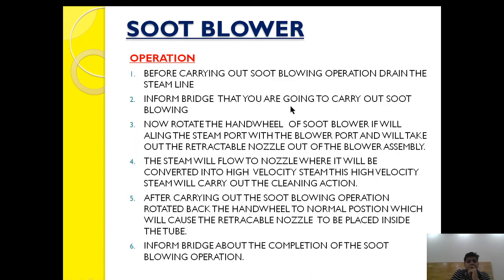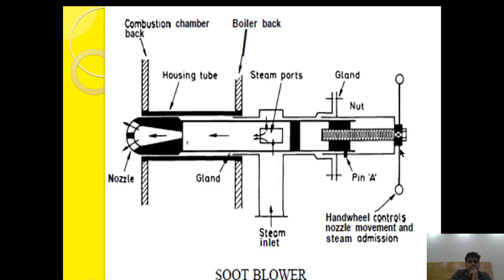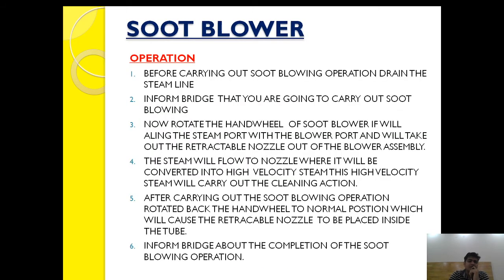Before carrying out the soot blowing operation — before you rotate the hand wheel to align the steam port with the steam inlet port — we should keep some things in mind. First: drain the steam line. This is very important because soot blowing is carried out only twice or thrice a day. As it is not a regular operation, the steam in the line may condense and change into water, which if steam is suddenly opened will cause hammering. To prevent that, we drain the steam line first.